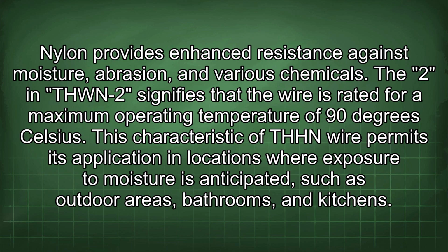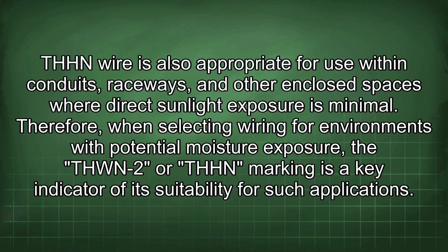This characteristic of THHN wire permits its application in locations where exposure to moisture is anticipated, such as outdoor areas, bathrooms, and kitchens. THHN wire is also appropriate for use within conduits, raceways, and other enclosed spaces where direct sunlight exposure is minimal. Therefore, when selecting wiring for environments with potential moisture exposure, the THWN-2 or THHN marking is a key indicator of its suitability for such applications.